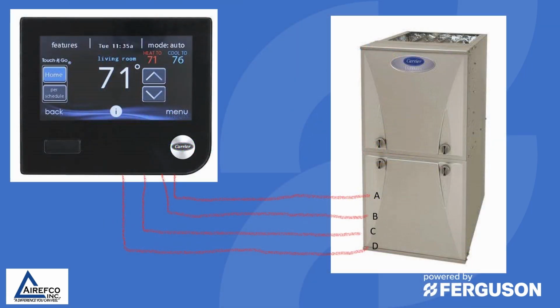So as we stated previously, the first thing you want to do is make sure that you have a communicating indoor furnace or fan coil. For a communicating system, the indoor equipment must be a communicating type equipment. Once that is established, then you want to check your wiring between the indoor unit and the user interface to make sure that the ABCD connection is landed in the proper place and your connections are tight.